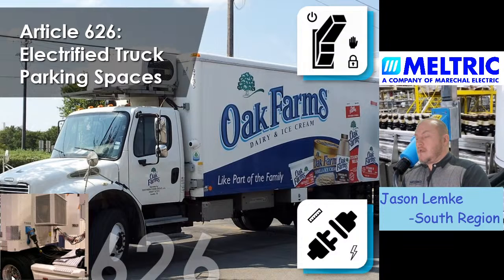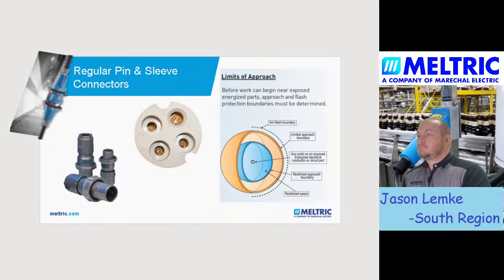So whenever you have an exposed conductor, you will have an associated limited approach boundary, which is what we talk about these days, where you will need to make sure that only qualified people are within that restricted space. With a pin and sleeve device, you will have an exposed conductor, and all conductors that are exposed that have not been verified de-energized will have this restricted space around it.